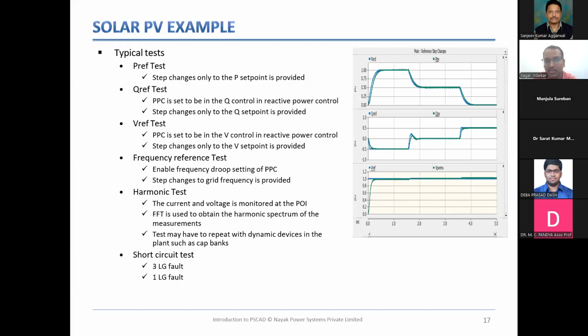So to perform the harmonic test, you will measure the harmonic profile of the inverter. Then the same harmonic profile will be modeled in PSCAD as current injection. So if there are 100 converters, you'll model 100 current injections, and then you'll model the plant devices, the cables, transformers, and ultimately you will measure the harmonic distortions at the POI, and check whether the distortions are within the safe limit. If they're violating, then again you'll have to deploy certain mitigation devices. These are basically passive filters. So if you have a fifth harmonic problem, you'll install a fifth harmonic filter, and after the filter, you'll check whether the harmonics are within the IEEE 519 standard.